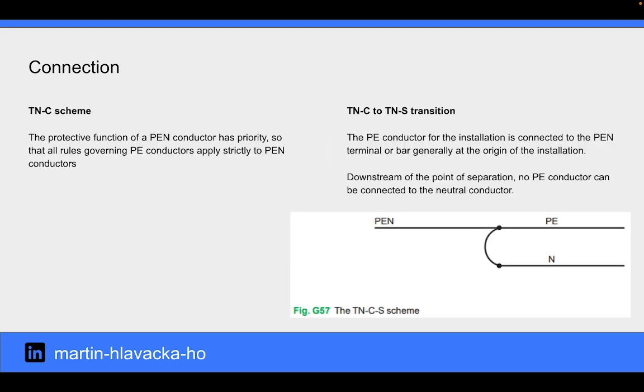In the TN-C scheme, the protection function of a PEN conductor has priority, so all rules governing PE conductors apply strictly to PEN conductors. During the transition from the TN-C scheme to the TN-S scheme, the PE conductor for the installation is connected to the PEN terminal or bar, generally at the origin of the installation. Downstream of the point of separation, no PE conductor can be connected to the neutral conductor.